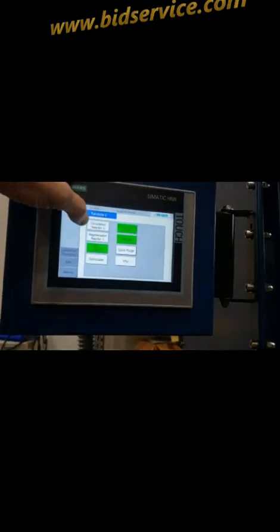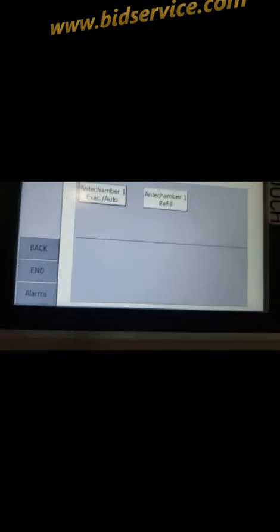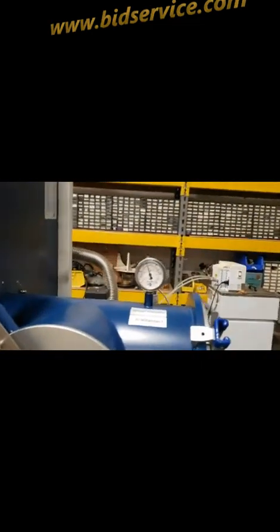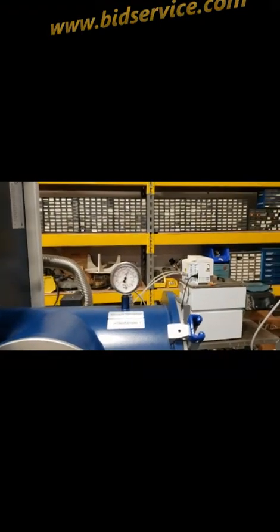Okay. And then finally, you do have the analyzer you can turn on and off. You can see it says switched off. We'll turn that back on. We'll turn our circulator back on. We'll look at some additional functions. You can run your antechamber from here. That's in auto mode. Evacuate refill. I'll talk about that later. And you can also do a refill, which I'll do now. And like I told you before, it's refilling from the box. And as you can see, the gauge is going down.